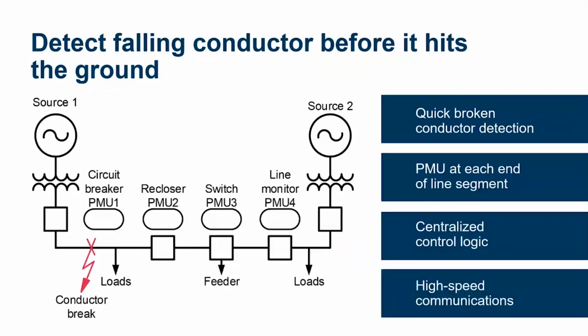Now, I'm going to talk just briefly about what we call the falling conductor detection system. We wrote a paper, partnering with San Diego Gas and Electric back in 2016, about this type of system. This is completely separate from AST. This system utilizes low latency communication between phasor measurement units to quickly detect a broken conductor and trip the circuit before that conductor hits the ground.